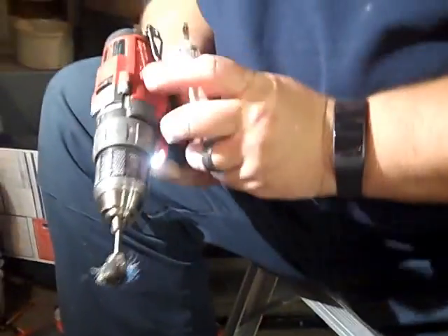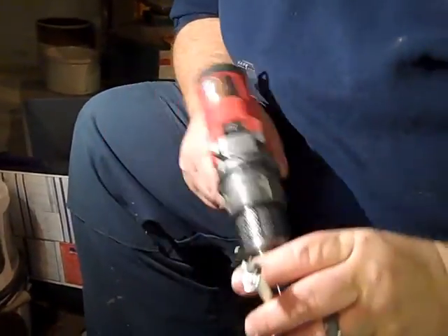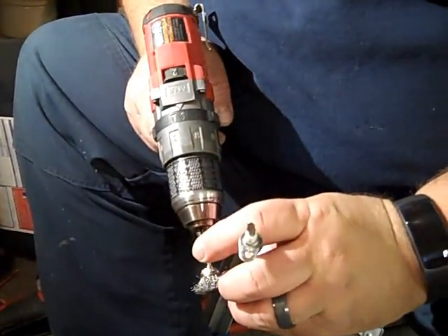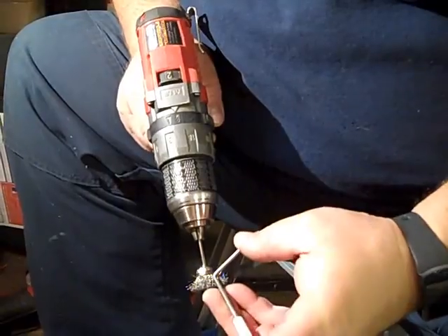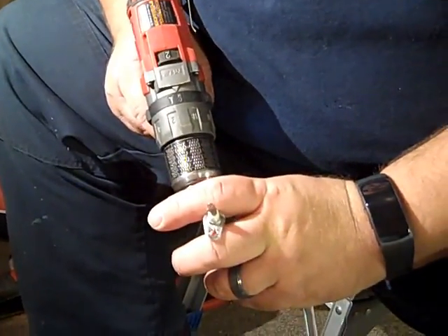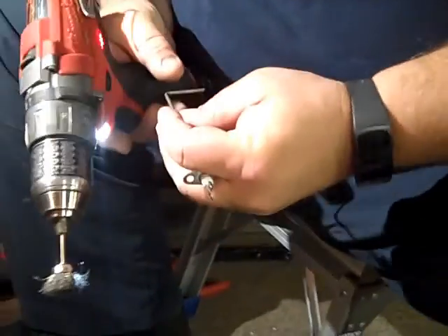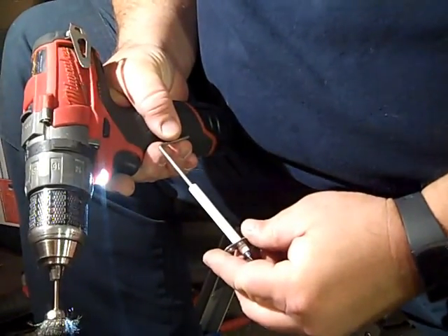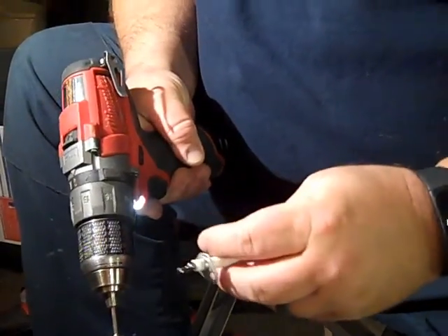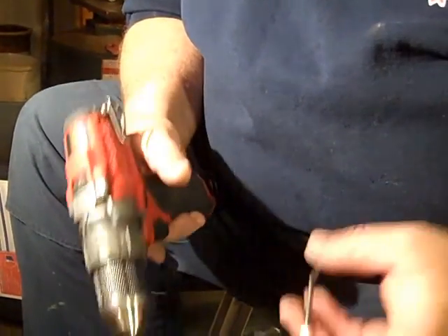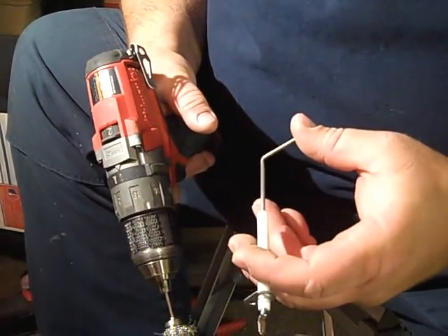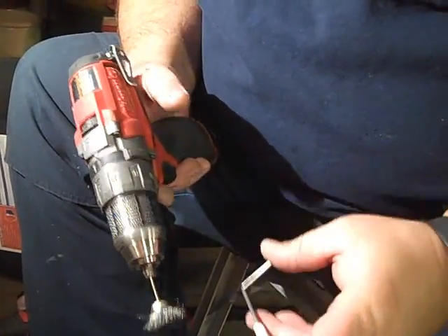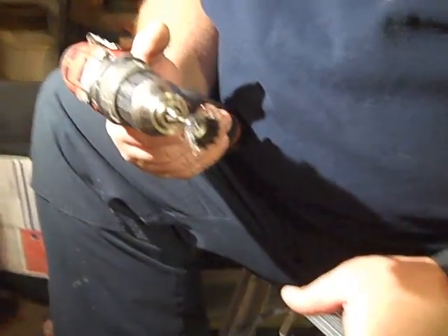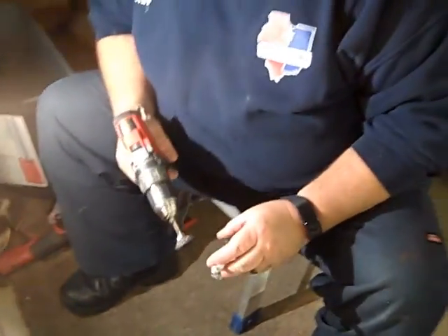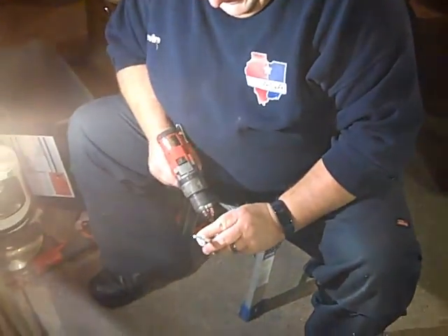Alright, now Kevin's doing one of the most important things: he's cleaning the flame sensor, because without that flame sensor being clean, it may not register a flame, and as a consequence the burners will shut down within a couple of seconds of the gas valve opening. One important thing to remember, as I've told you before: do not use sandpaper, use a wire brush. Isn't that correct, Kevin? Yeah, I always use a wire brush. They say sandpaper leaves silicates behind on the rod, which hampers conduction of electricity through the flame. So using a stainless steel brush, if anything, I'm leaving stainless steel residue on stainless steel. Exactly, and that way it works real well.